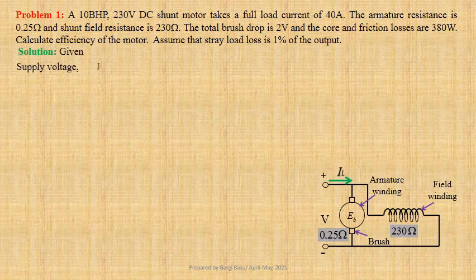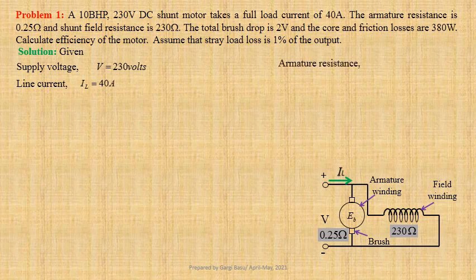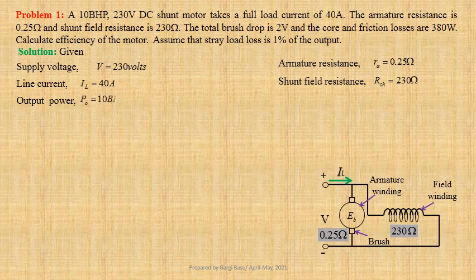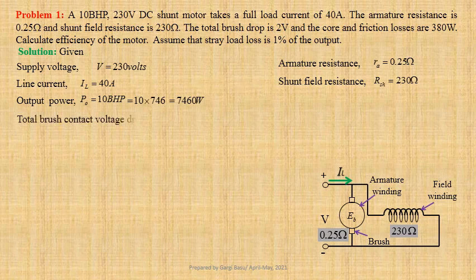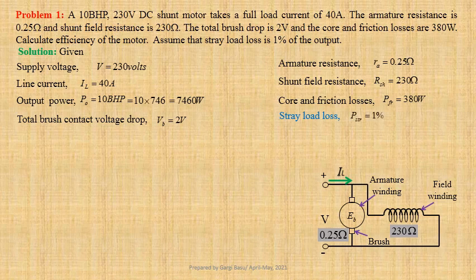Supply voltage V equals 230V. Line current IL equals 40A. Armature resistance RA equals 0.25Ω. Shunt field resistance RSH equals 230Ω. Given output power PO equals 10 BHP. Since 1 BHP equals 746W, PO equals 10 × 746W equals 7460W. Total brush contact voltage drop VB equals 2V. Core and friction losses PFR equals 380W. Stray load loss PSTR equals 1% of PO, equal to 0.01 × 7460W, that is 74.6W.